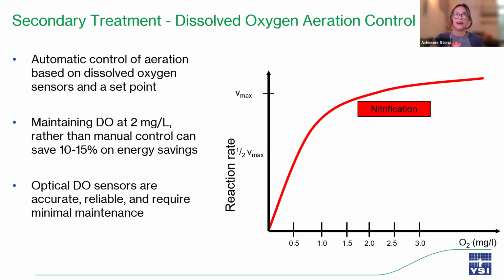The highest cost typically of operating a wastewater plant is the cost of running blowers for aeration in your aeration basins. And if blower speeds are not controlled and instead set to some specified airflow output, then chances are a lot of money and energy is being wasted on running those blowers. So the most common control scheme used in secondary treatment is dissolved oxygen aeration control. In this control scheme, blower speed is adjusted on a VFD to maintain a DO concentration set point in your aeration basin. So we're using online DO sensors to control our blowers and maintain a DO set point. The most common set point is 2 milligrams per liter DO.